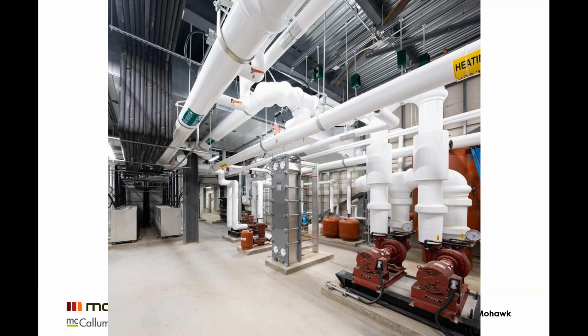I also left this picture in as an interesting piece. There was a heat exchanger proposed for the air handling system. There's only one air handling system for the entire building, and we do capture and use reclaimed heat through an enthalpy wheel in the air handling unit. The designers had proposed a heat exchanger here too - you can see there were ports at the top and bottom that would connect to the air handling system. But in the end they felt they didn't need it, though it got installed anyway. So when I'm touring people through, I just say it's a piece of architectural art designed into the facility, and people get a kick out of that.